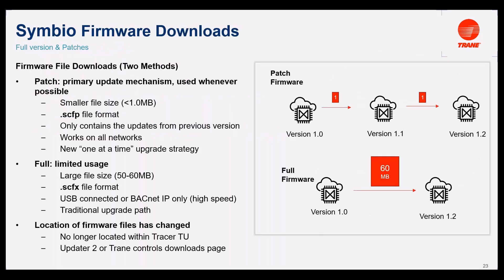Full version and patches — we have two ways to upgrade our Symbio controllers. The first one is the patch. It's the primary update mechanism; use it whenever possible. These patches are smaller file sizes, less than one megabyte. The format is SCFP and only contains the updates from the previous version to the new version.